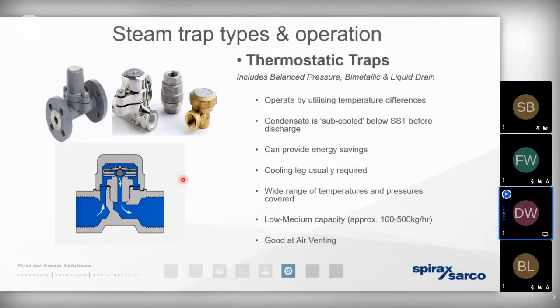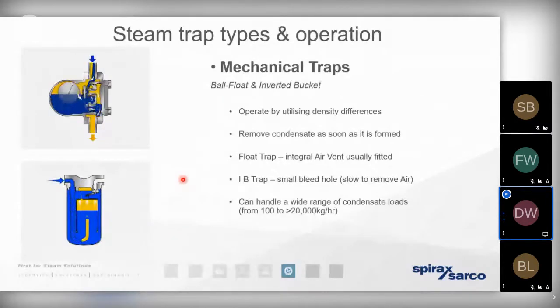The thing to bear in mind is that the cooling leg should be unlagged, and it is designed with the intention of allowing that condensate to cool down. And then we've got the mechanical traps, and the mechanical traps work on the density principle. It could be the float trap, as you can see at the top of the screen, or it could be the inverted bucket trap that you can see at the bottom of the screen. They both work on the density principle.